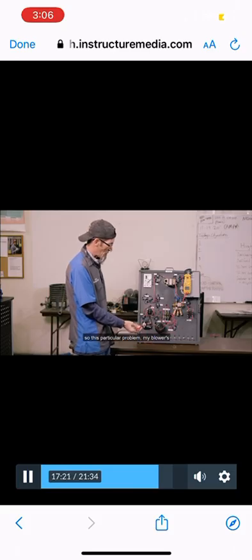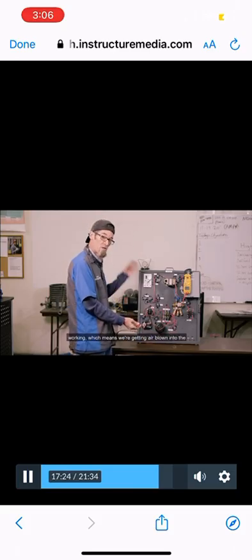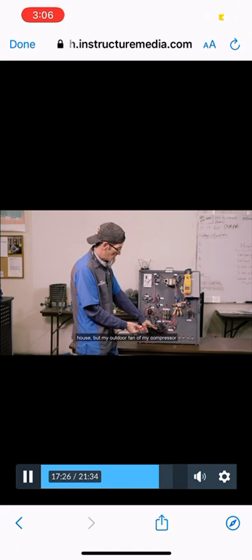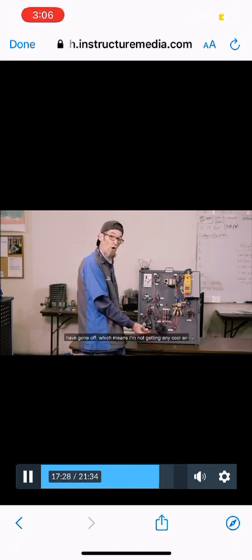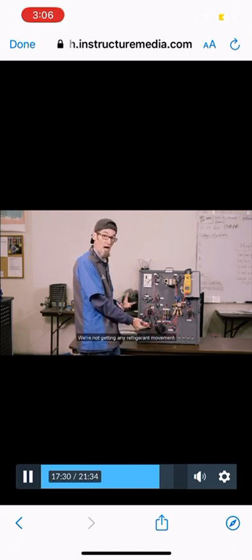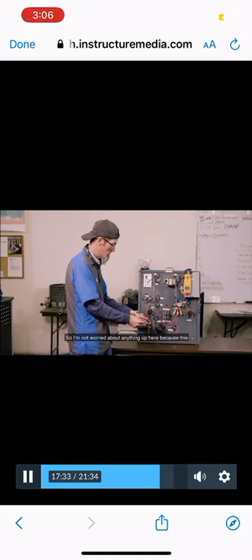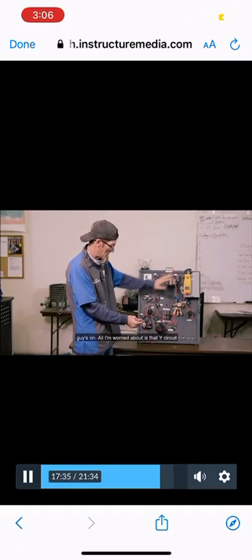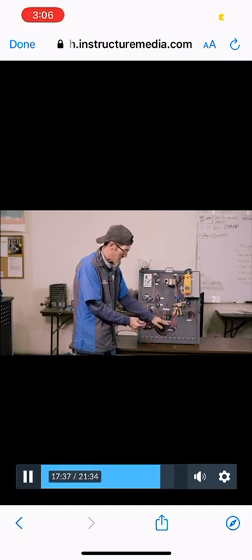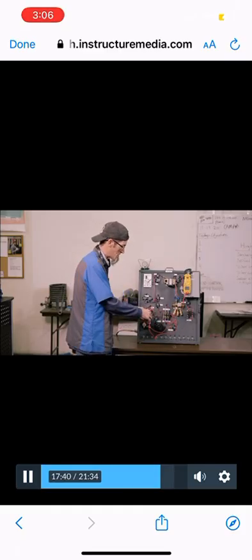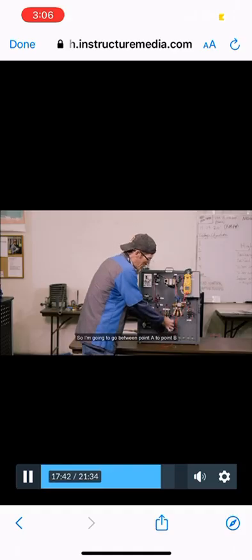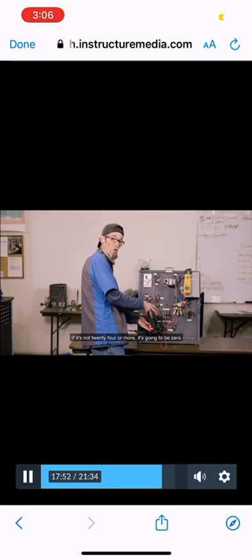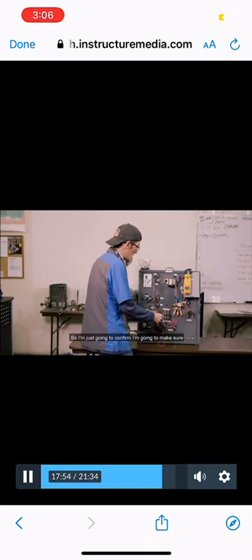Okay, so this particular problem, my blower's working, which means we're getting air blown into the house, but my outdoor fan and my compressor have gone off, which means I'm not getting any cool air in the house. I'm getting hot air. We're not getting any refrigerant movement. So I'm not worried about anything up here because this guy's on. All I'm worried about is that Y circuit, the one that turns this contactor on. So I'm going to go between point A, point B, and I'm looking for some voltage. And I got 6 volts. Here's the deal in this field. If it's not 24 or more, it's going to be 0. So I'm just going to confirm.